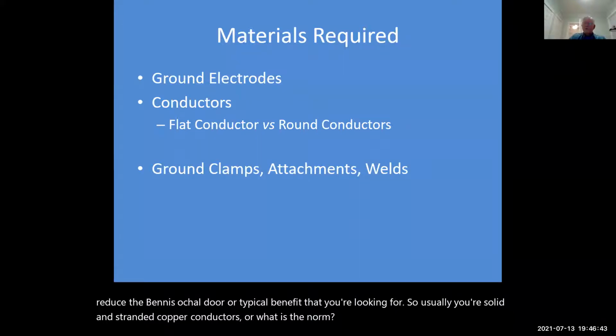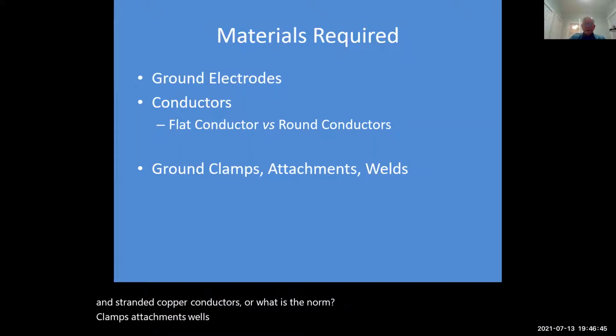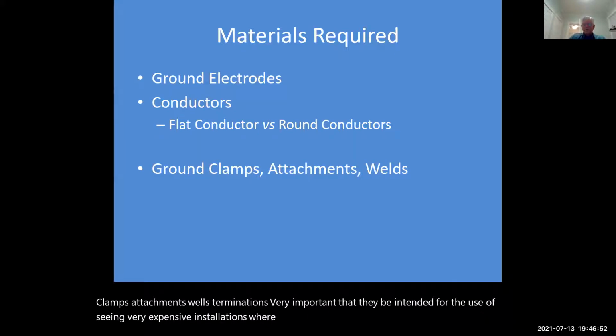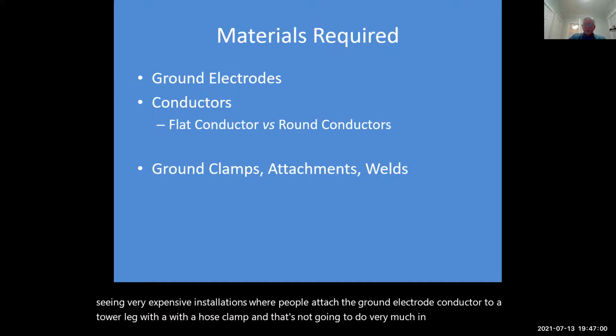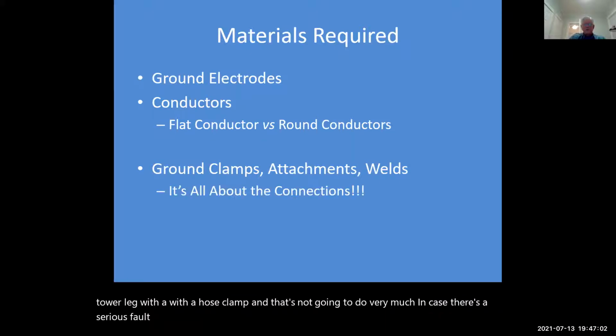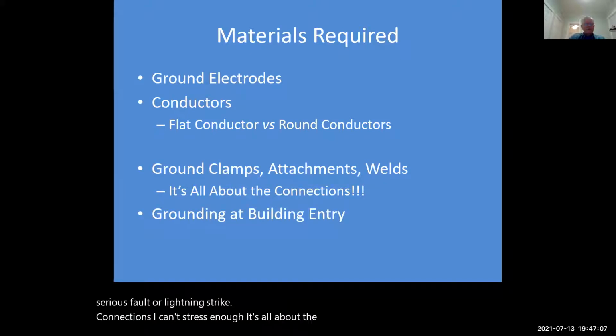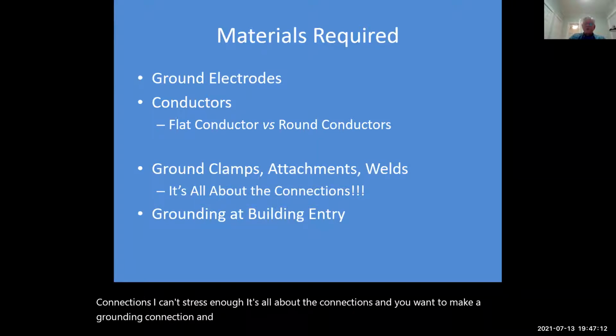Clamps, attachments, welds, terminations, very important that they be intended for the use. I've seen very expensive installations where people attach the ground electrode conductor to a tower leg with a hose clamp, and that's not going to do very much in case there's a serious fault or lightning strike. Connections, I can't stress enough. It's all about the connections, and you want to make your grounding connection and bonding connection at the building entry. You want to take it off the low point if it's a tower, not halfway up.